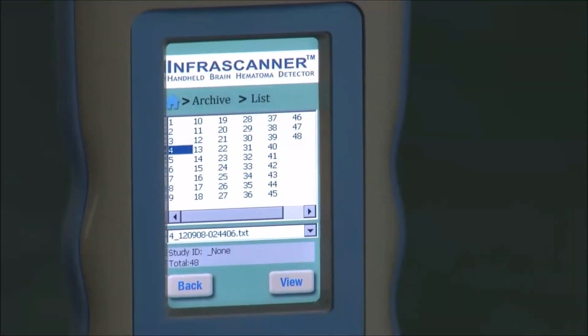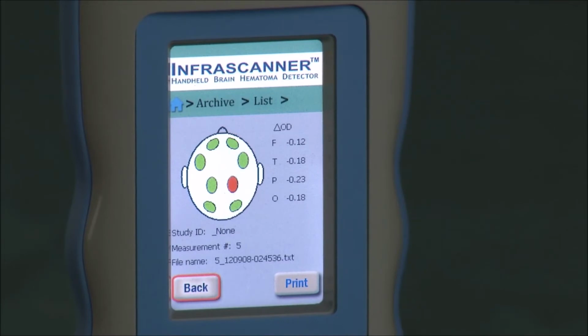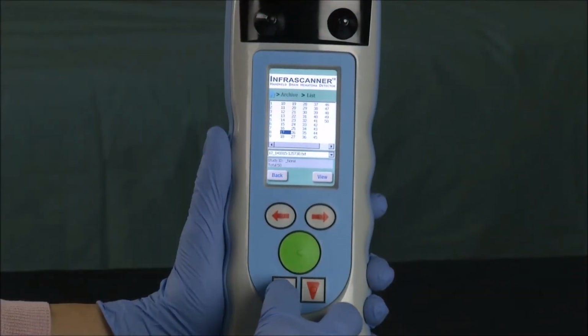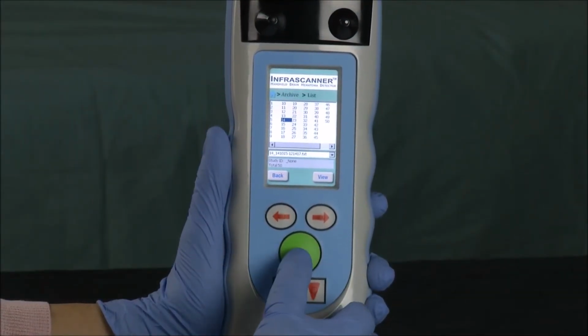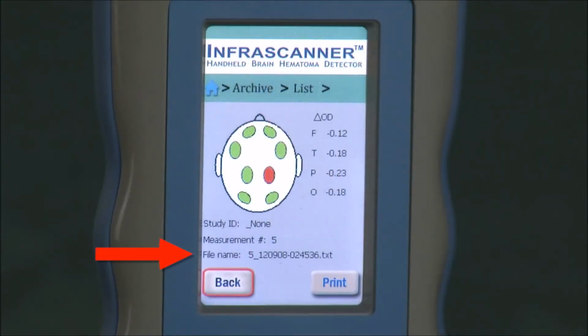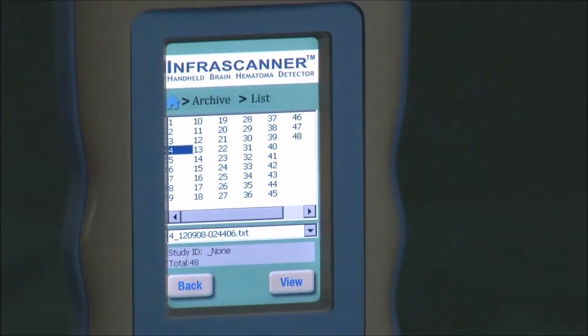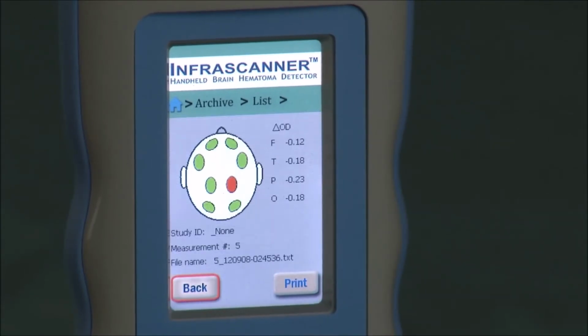The archive screen is where measurements are stored. By selecting View and using the up-down arrow key to select the scan to be reviewed, the scan measurement will be the number followed by the year, month, day, hour, minute, and second. When the measurement number is selected, the head diagram, along with the relative optical density number at each measurement point, can be reviewed.